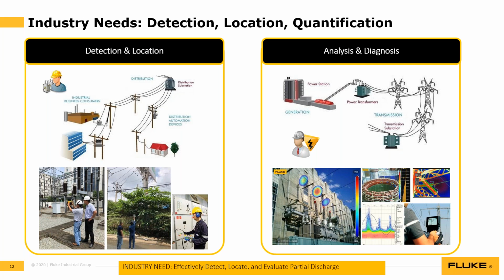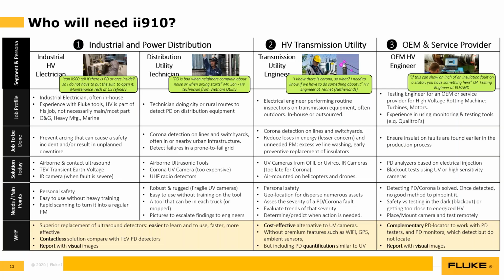The one on the right is then this analysis and diagnosis, which is also a need usually for a slightly different customer, different persona, but they want to know what type of partial discharge it is, or other aspects like the pulse number or the PRPD plot. So we have some of that built into the ii910, but I would say our detection and location is where we shine the most. Another view of the needs is by persona breakdown. And once again, we're looking at detect and locate for power generation and distribution. There's also the OEM side, which is number 3 there. And I'll show some examples of that later.